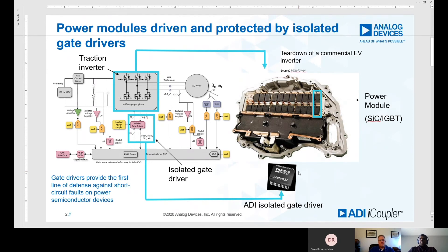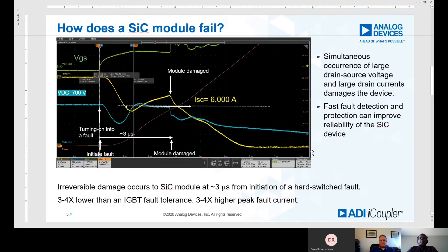That's a really good question. We've done quite a bit of testing in our labs on the bench to find out the limits of the silicon carbide device. Typically, IGBTs can withstand faults for about 10 microseconds or so. What we're finding out is that silicon carbide modules are able to withstand for 3 microseconds.